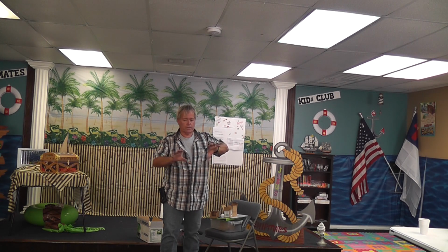So when you have a low voltage condition, instead of 208 coming in, you hit 200. Your 24 volt now drops down to 18. The coil of the contactor pulls a set amount of power. Now you have low voltage going to that coil. That board says we have low voltage, we have high amp draw off the coil, we must have a problem, and shuts the machine down. So if you take out a 60 amp contactor and put in a 75 amp contactor, the next size up, you're gonna keep locking out because it thinks there's a problem and there's not. So you have to watch what parts you put in and replace for the parts you took out. They've gotta be close to a match, or at least know what you're doing with it.